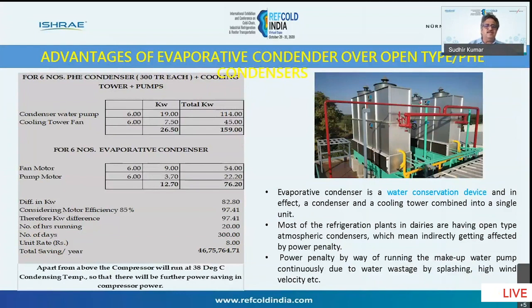A small illustration has been given, using an evaporative condenser versus a cooling tower and PHE condenser. Even though the calculation shows this is for a 300 TR plant, if you have a 1000 TR plant, then definitely you will have a better advantage in using evaporative condensers.